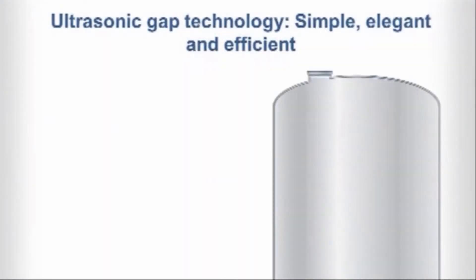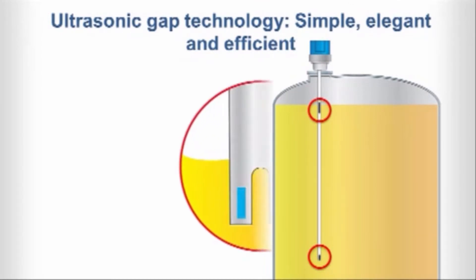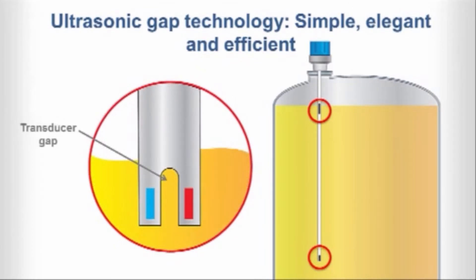The pulse signal technology utilized by our Echotel Models 961 and 962 switches can easily handle your most challenging process conditions. Pulsed sound waves are transmitted across a transducer gap when liquid media is present, but are attenuated when the gap is dry. When liquid is present in the gap, a receive crystal senses the ultrasonic signal from the transmit crystal and converts it back to an electrical signal, which is then sent to the electronics to indicate the presence of liquid. This simple, elegant, efficient process is also called ultrasonic gap technology.